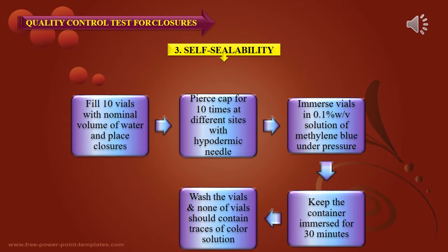For the self-sealability test, fill 10 vials with nominal volume of water and place closures. Pierce the cap 10 times at different sites with a hypodermic needle. Immerse vials in 0.1% w/v solution of methylene blue under pressure and keep immersed for 30 minutes. Wash the vials — no vials should contain traces of methylene blue color solution.